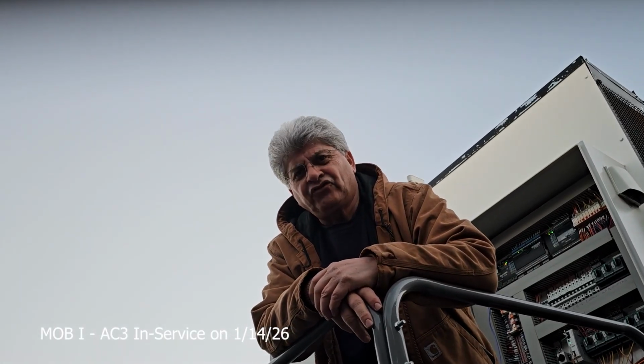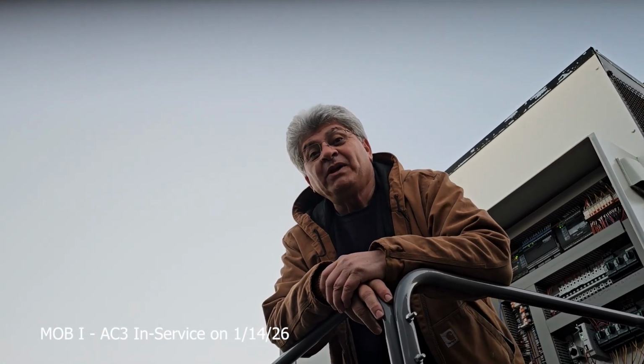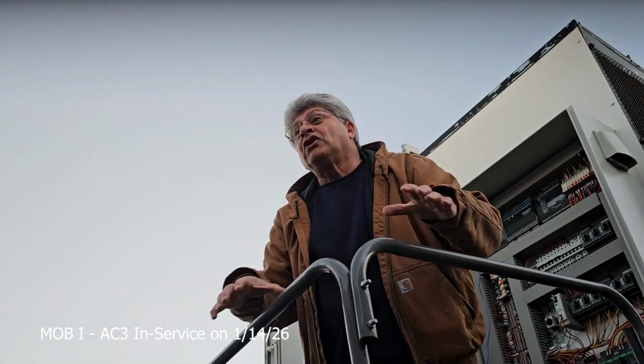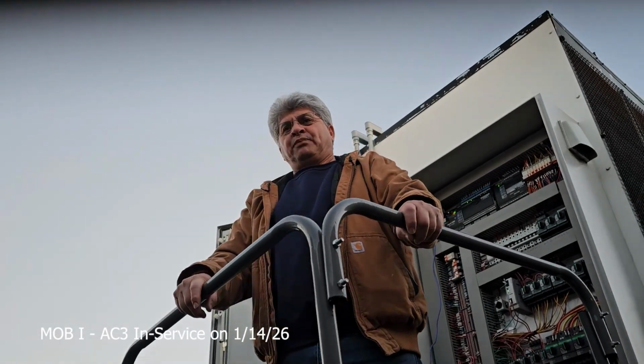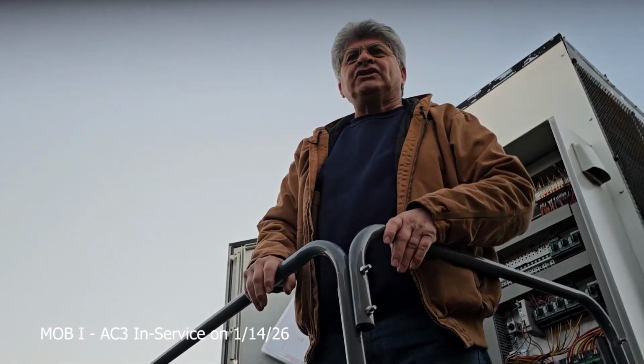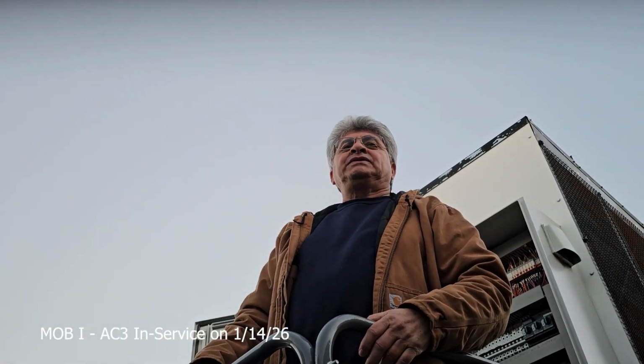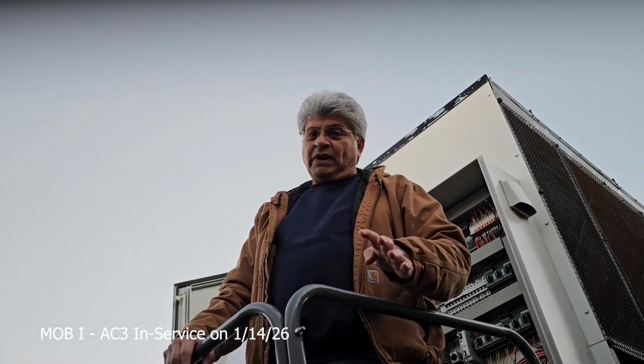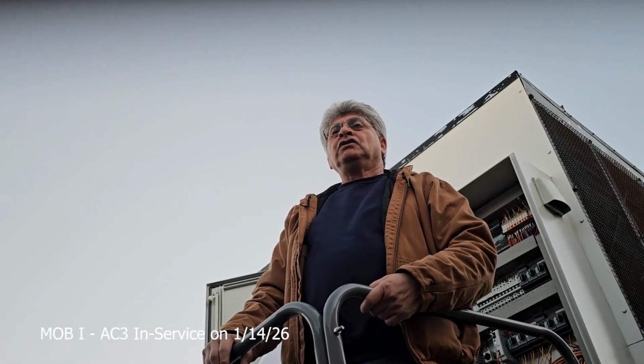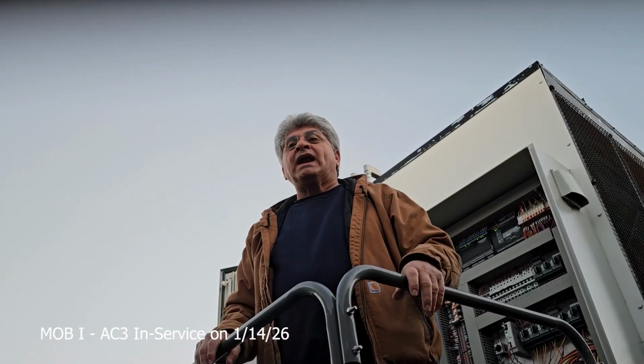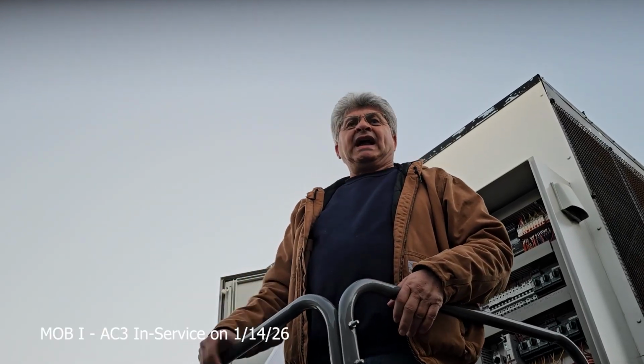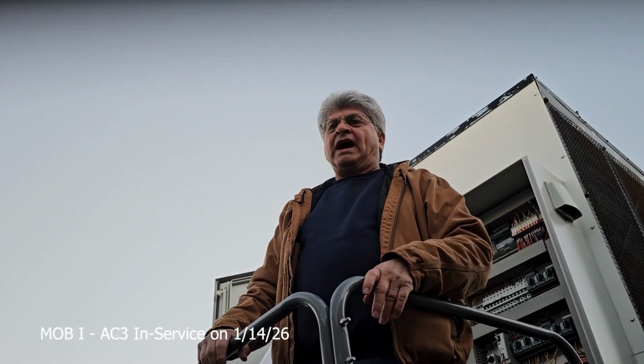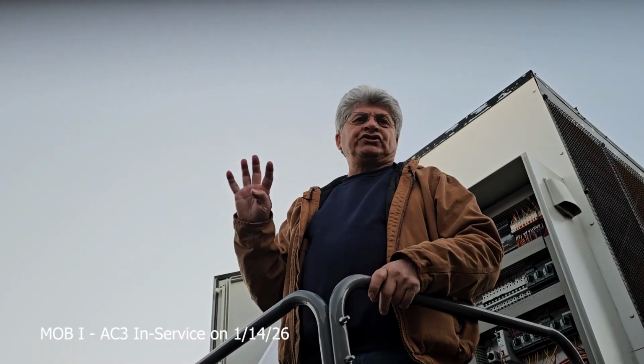Great question. What's the availability on those motors? You should have a parts replacement program. Sometimes they're made in the USA, and sometimes they can take 3 or 4 weeks to get. So order some spares. In your operation here, you'd want to have a spare supply fan motor and a spare return fan motor. You've got 3 return fans and 4 supplies.